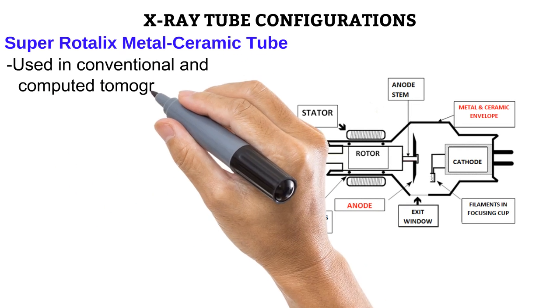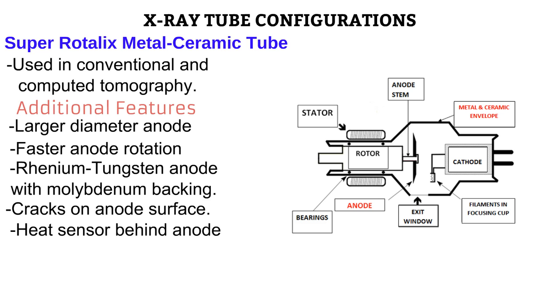Next up, the Super Rotalix Metal-Ceramic Tube. This is also useful in equipment that operate on high tube loading and short exposure times, such as cine radiography, serial radiography, conventional tomography, and computed tomography equipment. It also has the same anode modifications as in the heavy-duty tubes.